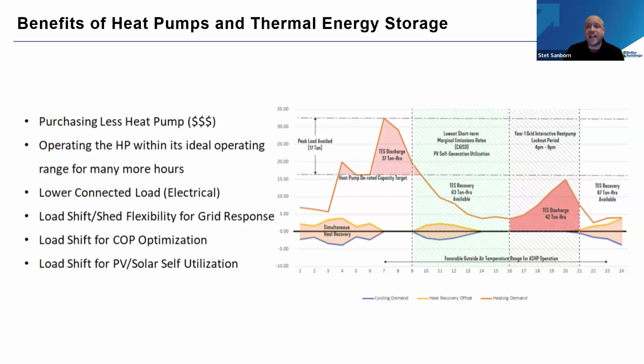In addition, all those non-peak days, like think of your shoulder seasons, you've got a lot of grid flexibility. So for those of you on a time of use meter, where your power might be really expensive or you pay really high demand charges, thermal storage allows you to shift your load to match that profile, so you can save even more money. So instead of a spark gap of electricity being 3 to 5 times more expensive than gas, you can shift your load until that cost is much more on par during off hours. So storage, thermal storage plus heat pumps are perhaps the most beautiful thing that you could possibly put on your project. Next slide.